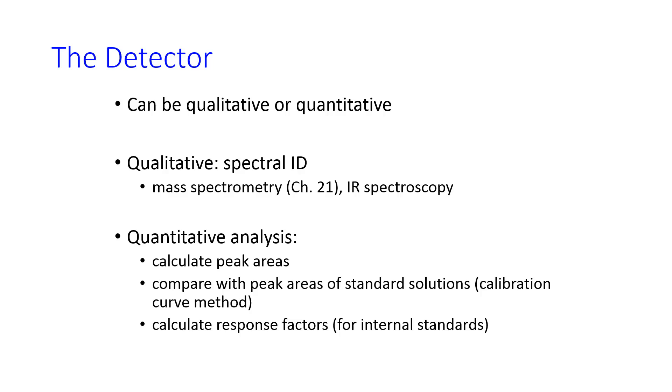Quantitative analyses have to be added to any kind of detection method that you use in order to relate the peak area that you get from the detector to the concentration of analyte that was in your original sample. You can either calculate response factors for internal standards, or you can create a calibration curve using peak area versus concentration.